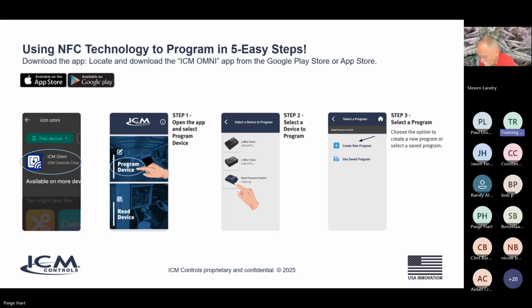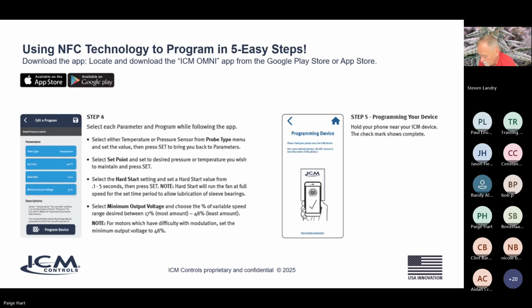And then you're going to create a new program. And this will start the process to create your new program. All right, and you'll come up to this screen, which will say edit a program. And you're going to select whether you're using a temperature probe or a pressure probe. And you're going to set that value in probe type. All right. And then you're going to go to the next feature, which is set point. And then you're going to select the set point. That's your pressure or your temperature that you want to maintain.